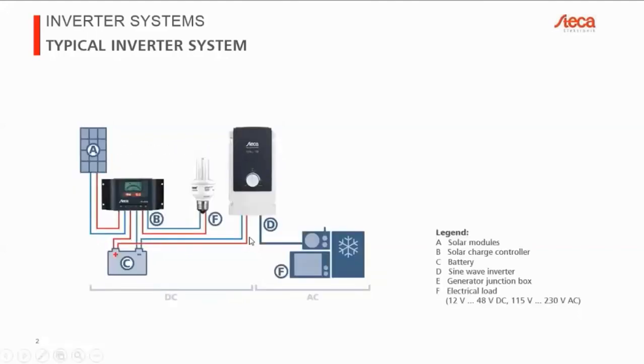So in this case, if you don't have a charge controller with an external current sensor, you would need to switch the charge controller to voltage control mode, not to state of charge mode. And this is a requirement as soon as you connect something directly to the battery, which again is required for the inverters. They must be connected directly to the battery. As soon as you do that, you need to switch the charge controller to voltage control mode if it is capable of doing a state of charge calculation.